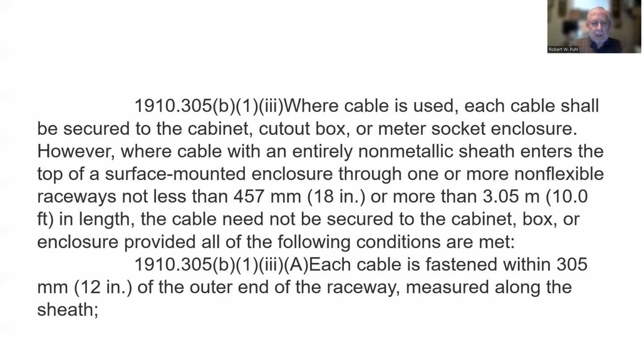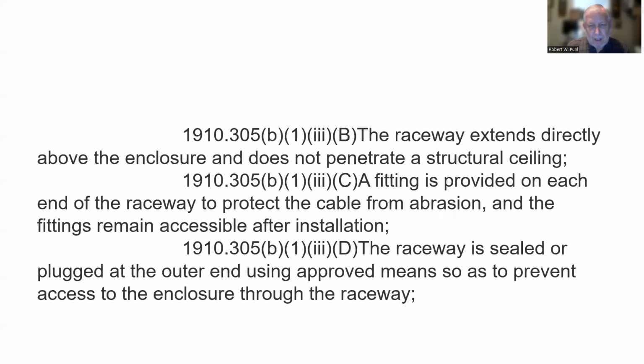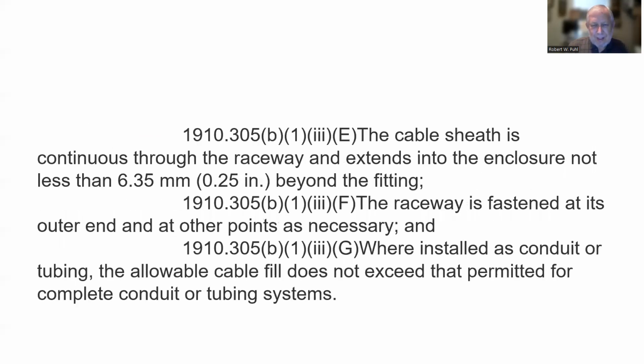Where cable is used, each cable shall be secured to the cabinet, cutout box, or meter socket enclosure. However, where cable with an entirely non-metallic sheath enters the top of a surface-mounted enclosure through one or more non-flexible raceways, not less than 18 inches or more than 10 feet in length, the cable need not be secured to the cabinet, box or enclosure, providing all the following conditions are met. And this is more of an installation thing, and I'm not going to get too much into electrical installations.